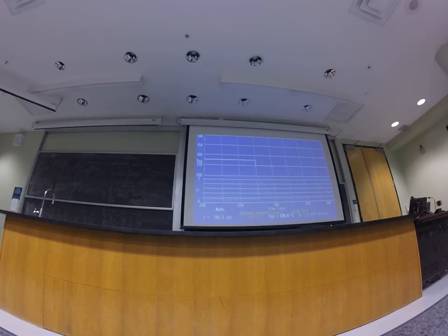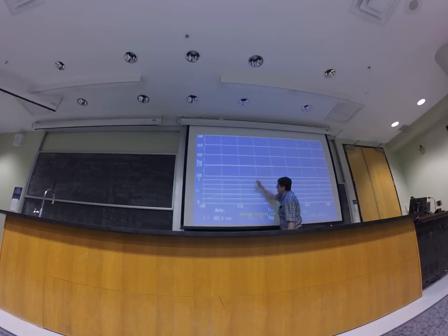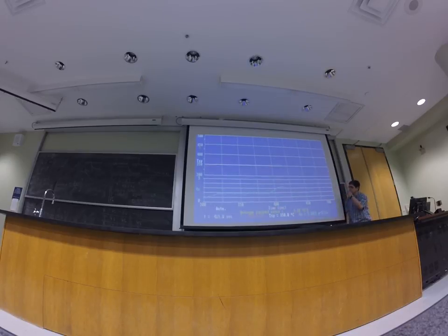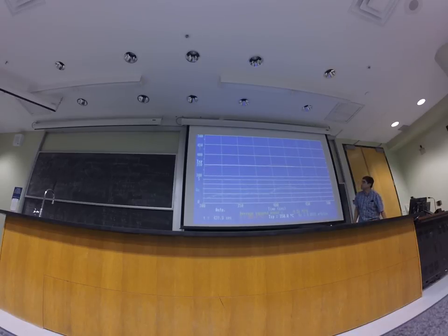There's a big set point change. We went immediately to the set point, with a little bit of overshoot. This is another indication of aggressive control. Aggressive control is typically taken care of by reducing the magnitude of Kc. Since I have considerable overshoot, this is an indication that my controller is tuned a bit too tightly. Here was a big disturbance. It returns nicely to the nominal value.